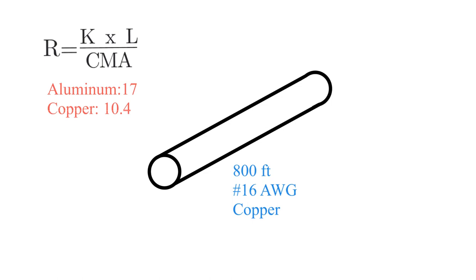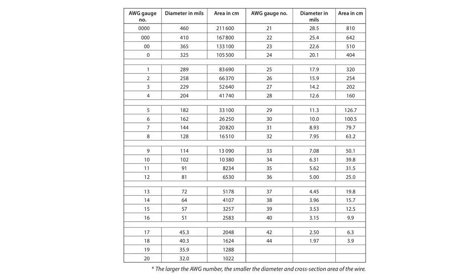So what we need to do for that is to go to our table. We go to our table here, and we see we've got our gauge number here. We go all the way down until 16. We move across here until we get to the area in circular mils. And it ends up being 2,583.